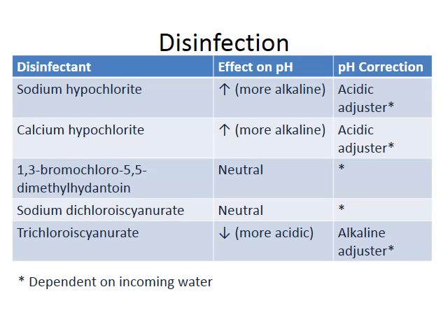The usual range of swimming pool disinfectants are applicable to spa pools. Each has their advantages and disadvantages, including the effect on pH. Typically, hot tub users will use solid chemical agents for ease of handling and dosing, and larger leisure complexes will use either sodium or calcium hypochlorite.